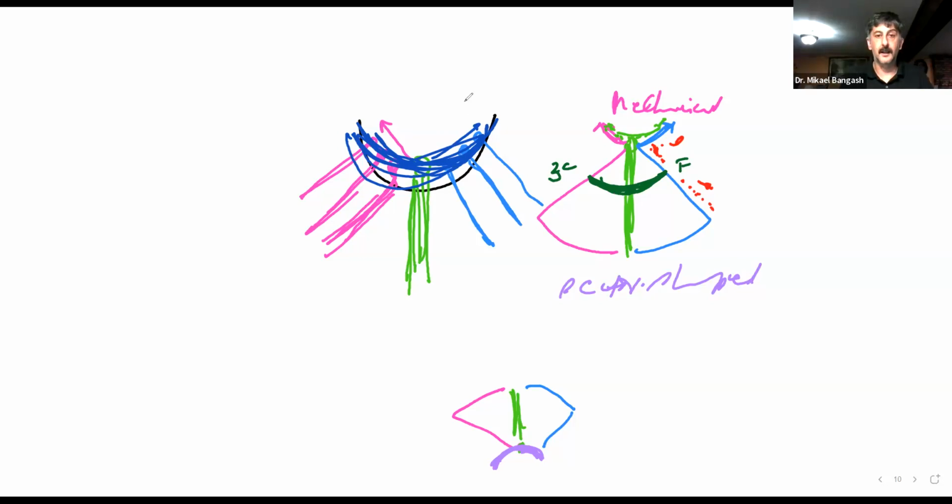Now, ladies, last question: what if you have a damaged PZT? What's going to happen, or what's going to be the effect on the image? There will be no image at all. Just think of it this way: the PZT is mainly what the transducer needs to create the sound waves that produce the image.